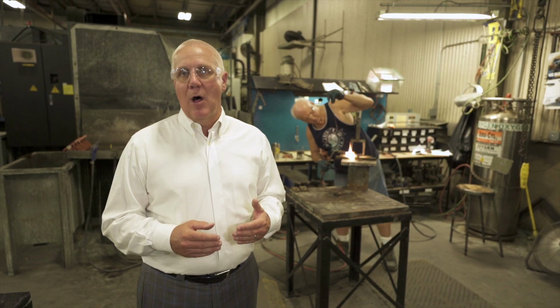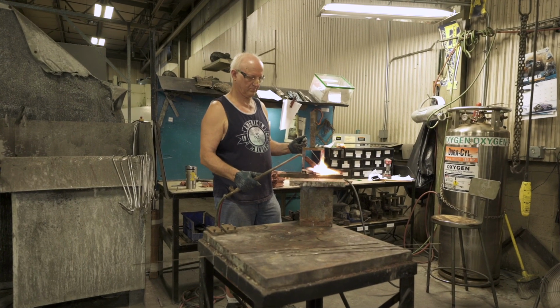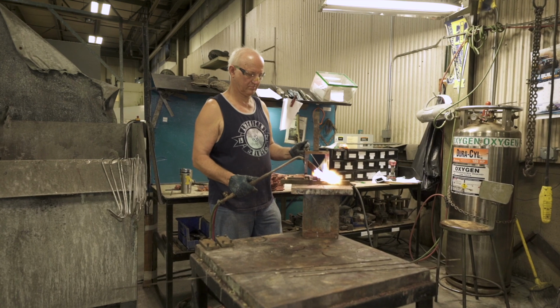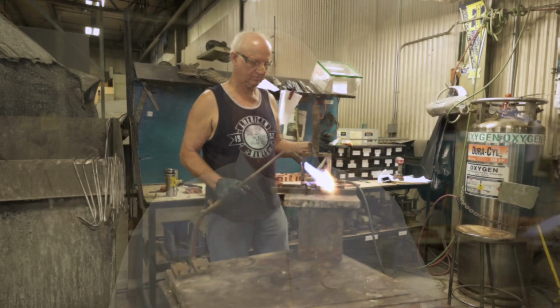First off is the quality of the electrical connection that's made by the braze joint. To accomplish that, we use a high silver content brazing material. And the second element is that of leak-tight joints. Again, the water cooling of our transformers is in the secondary, and if any of those joints leaks and the water comes in contact with the primary, the transformer will fail.